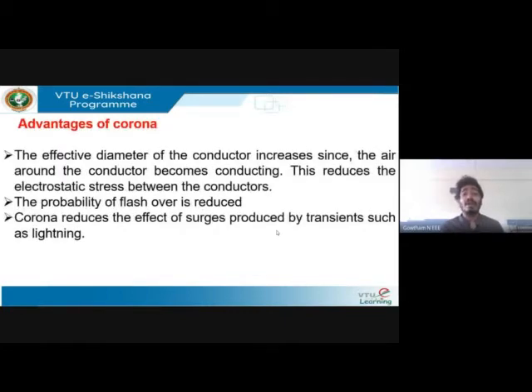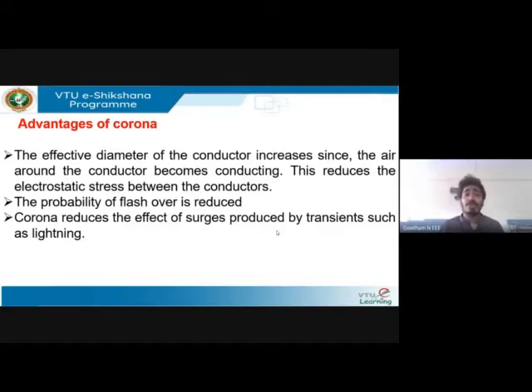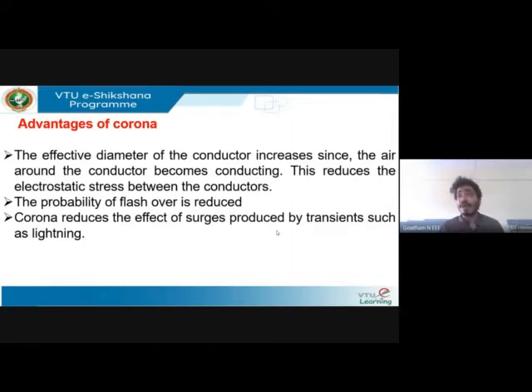Advantages of corona: the effective diameter of the conductor increases since the air around the conductor becomes conducting — this reduces electrostatic stress between conductors. The probability of flashover is also reduced. Corona discharge affects insulators, but it also reduces surges produced by transients such as lightning.